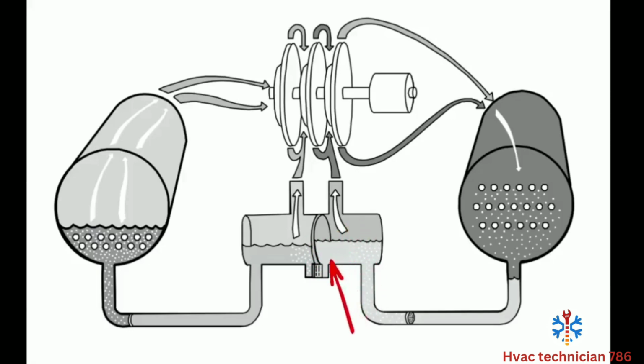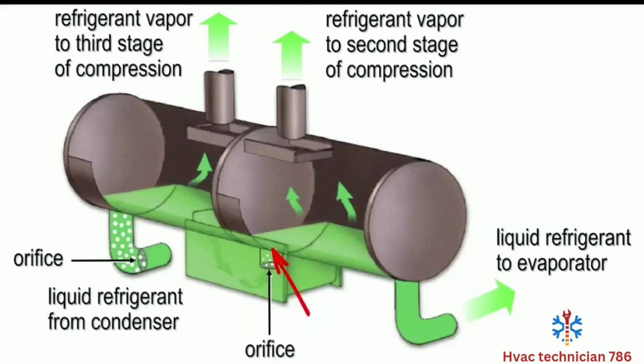Now, as the flash gas gets pulled into the compressor, the purified liquid refrigerant is going to be pushed through another orifice plate there at the bottom of the economizer. So as we come through, we go through this bottom chamber, through another orifice, and we're going to have a second stage of flash off. In our second stage of flashing, the refrigerant will then pull up into the second stage impeller, very much like what we saw with this CVHF. Going through this multi-step process helps improve our overall efficiency and the usefulness of our economizer, which makes our liquid refrigerant going to the evaporator more effective.